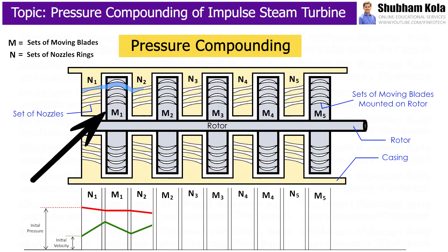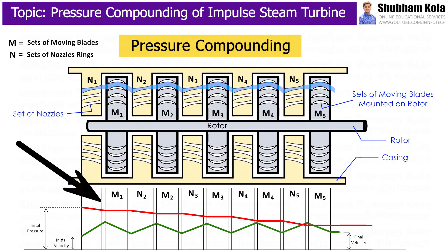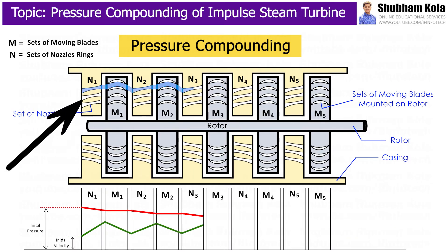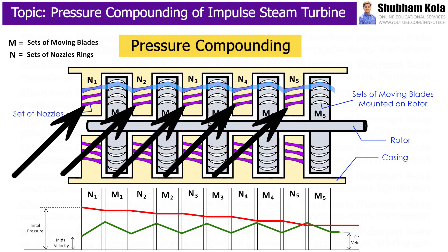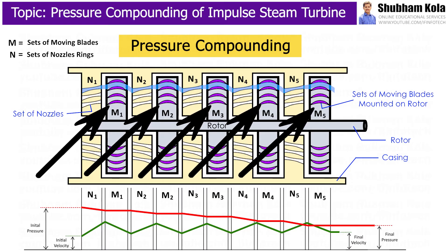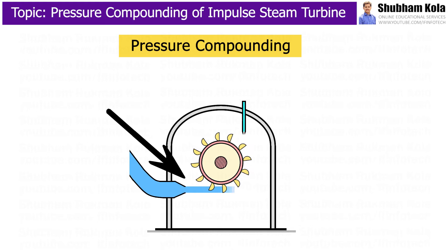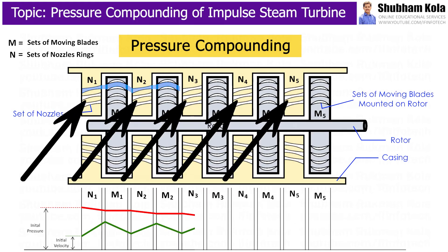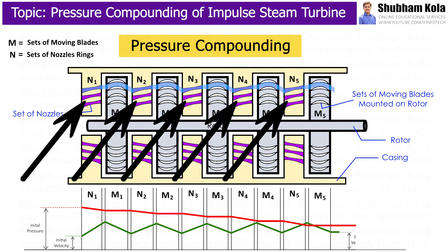It is the method of compounding a steam turbine in which the total pressure drop is divided into a number of stages. Here, expansion of steam takes place in more than one set of nozzles, and each set of nozzles is followed by a set of moving blades. The total pressure drop of steam does not take place in the first set of nozzles but is divided equally between all sets of nozzles.